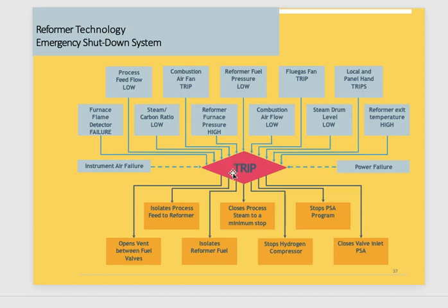Because the reformer is huge and critical and handling a huge amount of Q, thermal BTU, British thermal unit, maybe more than 20 or 30 million as calorific value, you have to shut down in the negative and in the positive, not like a normal heater where you shut down with the positive only at one value. You understand this? The draft related to the reformer is critical. You have maybe 4 trip values related to this draft.